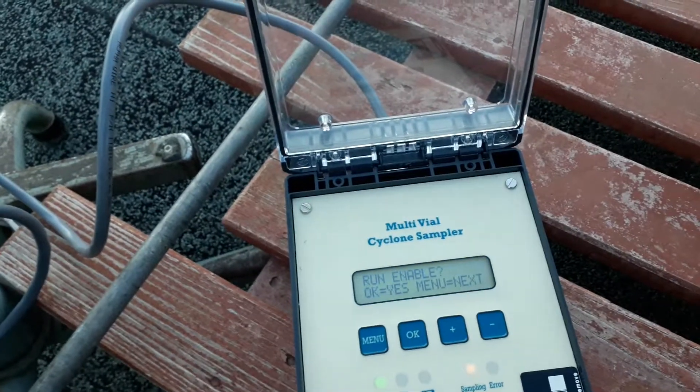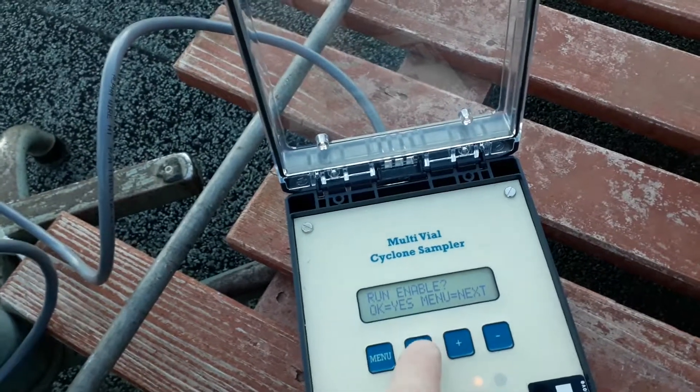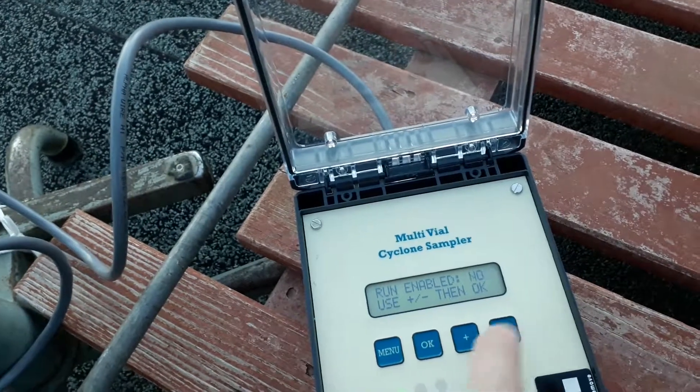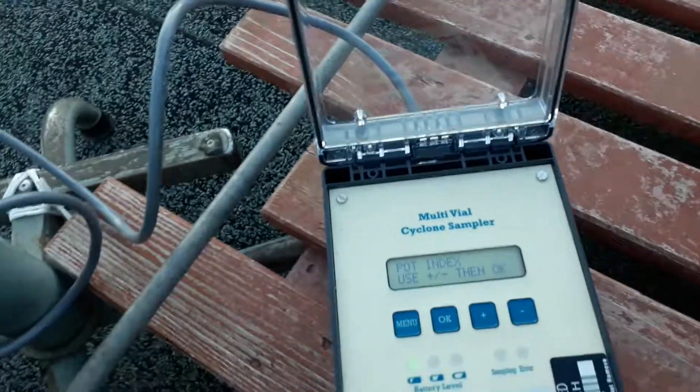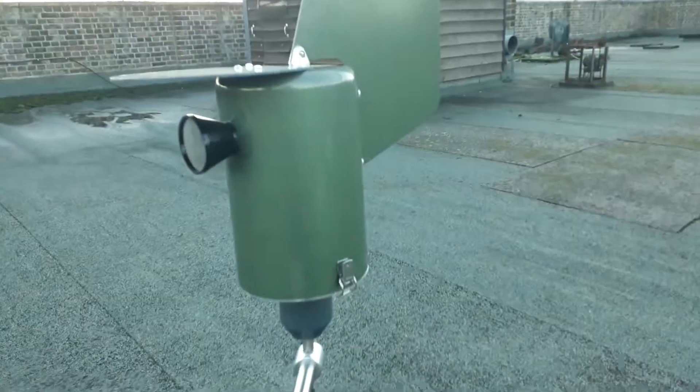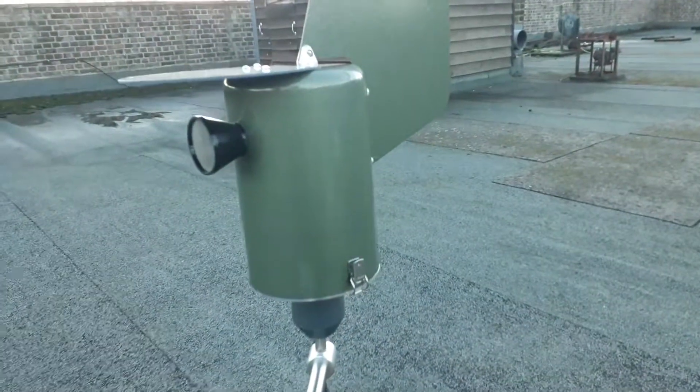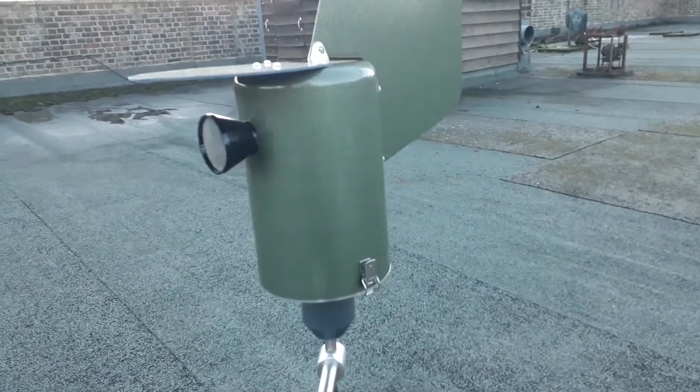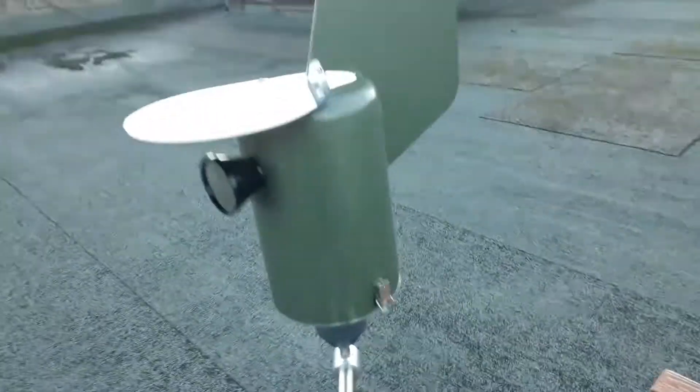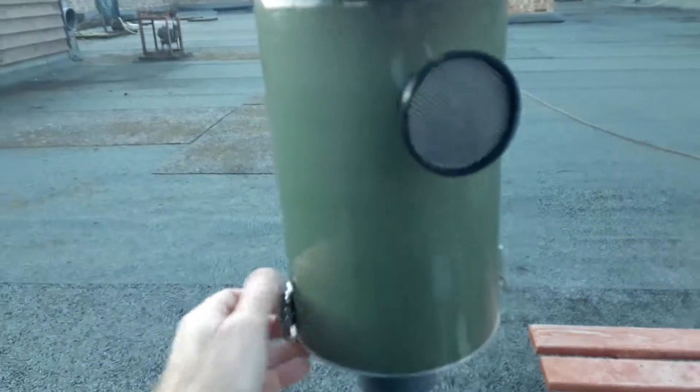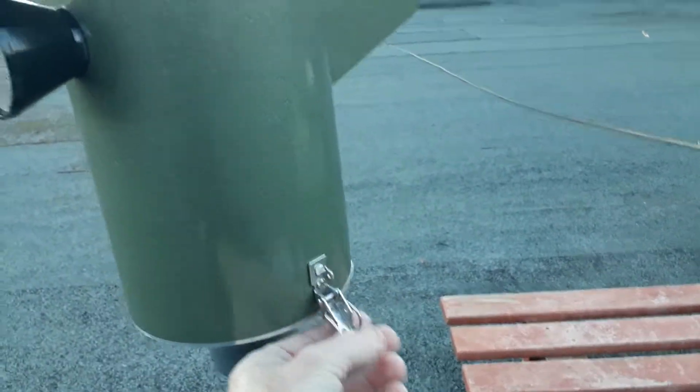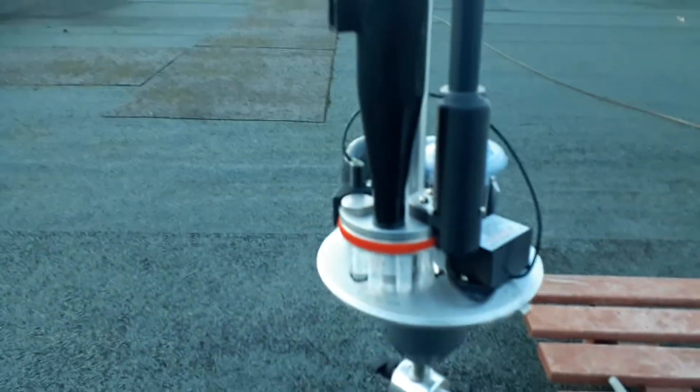this, click menu, run enable comes up, okay minus, okay. That stops the sampler. It's now free for us to change the tubes.